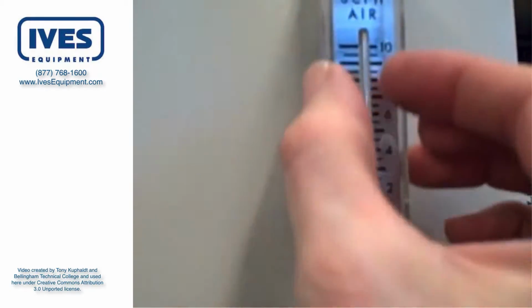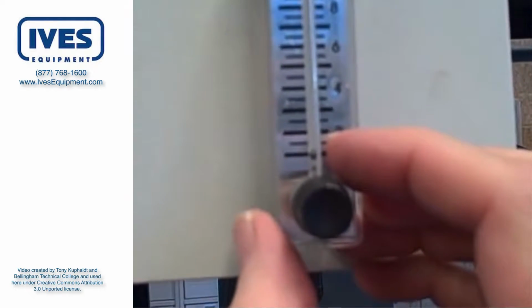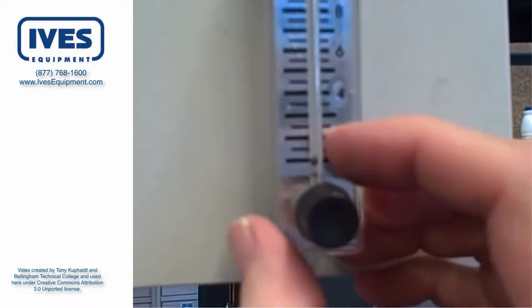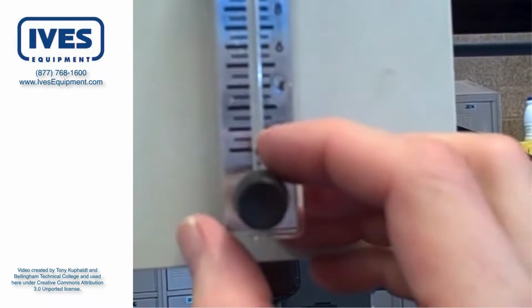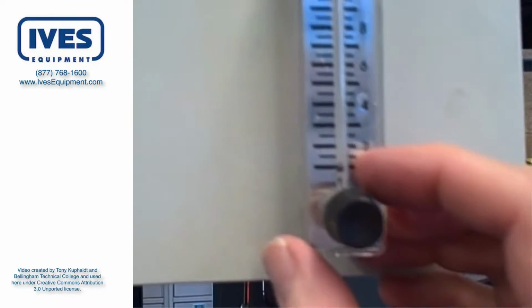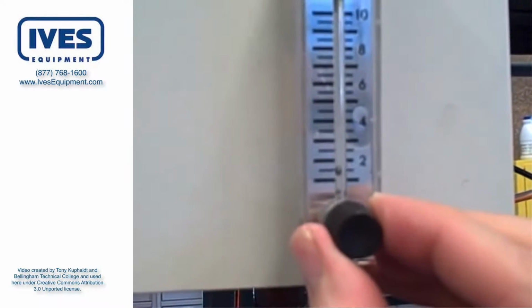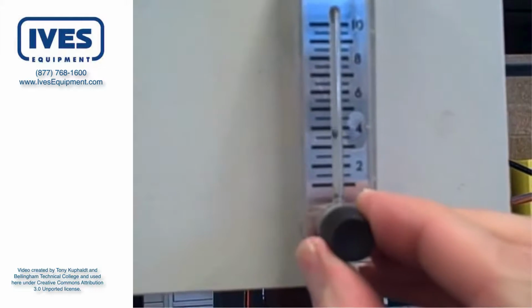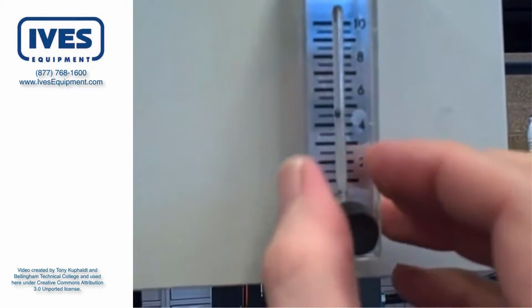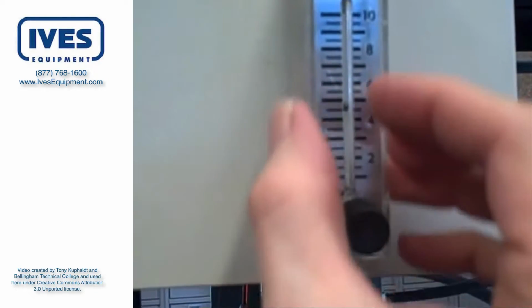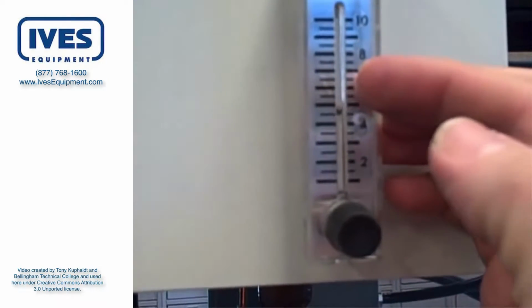that tube has a cone shape, starts small at the bottom and grows wider at the top. There's a small plummet inside that tube that's lifted up by the flow of fluid through it. Right now that plummet in this example is a small BB-sized ball of metal. And as I open up this valve, you can see that it rises up. Because the tube grows wider as it goes to the top, more fluid leaks by, and it takes a greater flow rate to lift that plummet to a higher level.